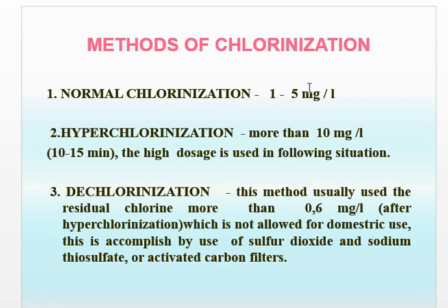The necessary dose of chlorine at chlorination by normal doses is determined in each case by carrying out a test chlorination, which accounts for the chlorine absorptivity of water. Minimal time of chlorine contact with water at chlorination by normal doses is in the summer not less than 30 minutes. Time of contact is increased up to 1 hour in the winter at low temperature.